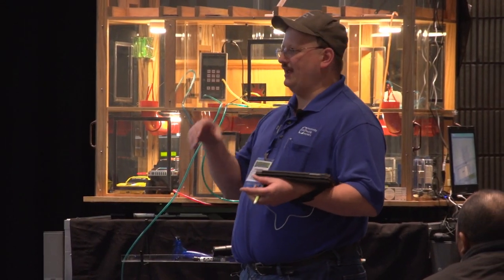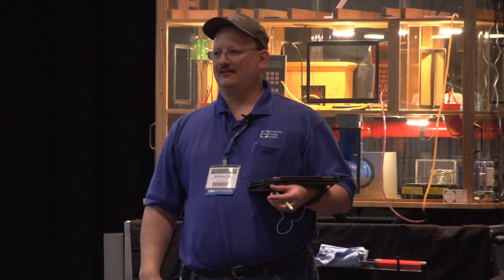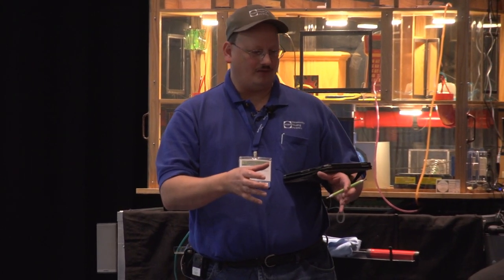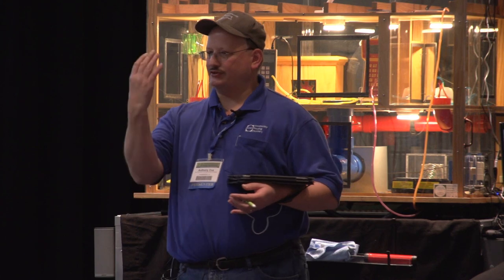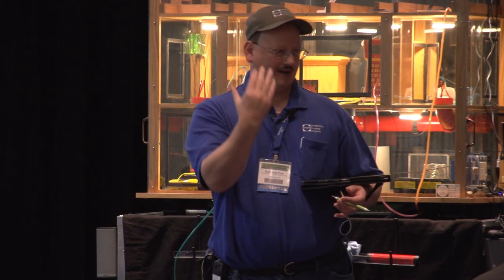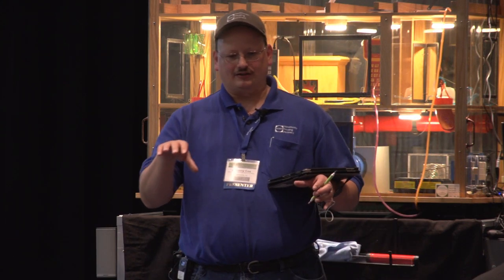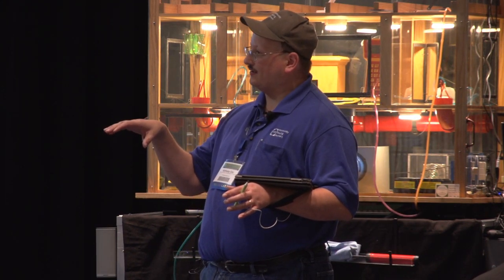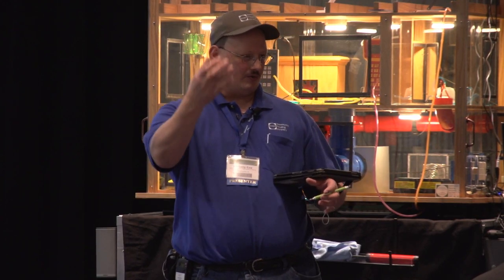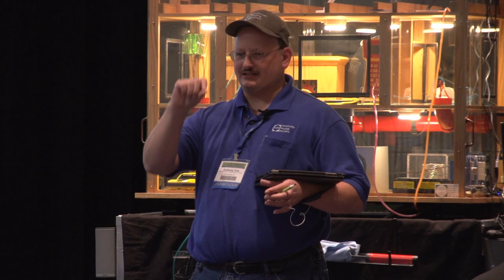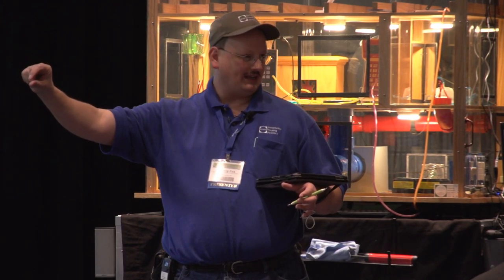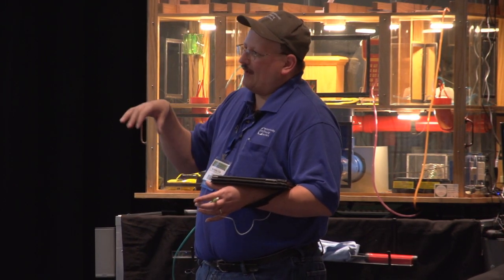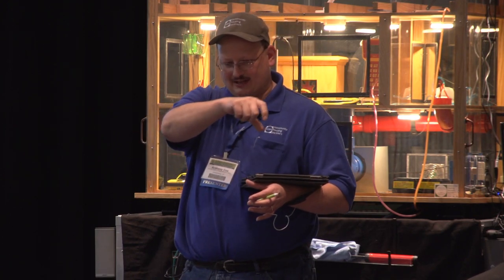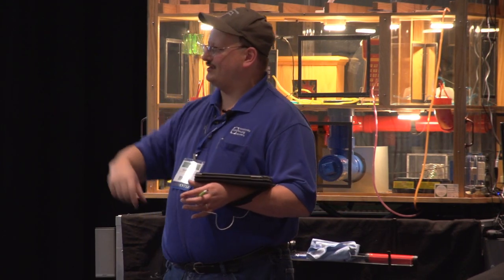Anybody ever take an infrared in the attic and pressurize the house? Does that work? I see a few hands. So if you pressurize and the house is warm and you're in the attic with the infrared, what would you see? You'd see brighter hot spots, right? I've heard of people who would air seal the attic, depending on your climate. If you missed the gap at the top plates, especially in a colder climate, and it's not a very big gap, is it? But if you add it up over the whole attic space, especially in a more extreme climate, that makes a big difference. I haven't done this myself, but when they pressurized the house, the top plates looked like train tracks through the insulation with the infrared.